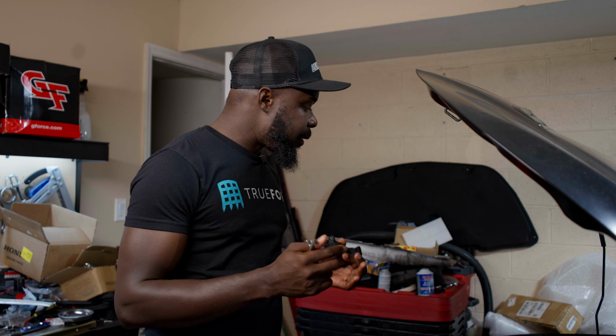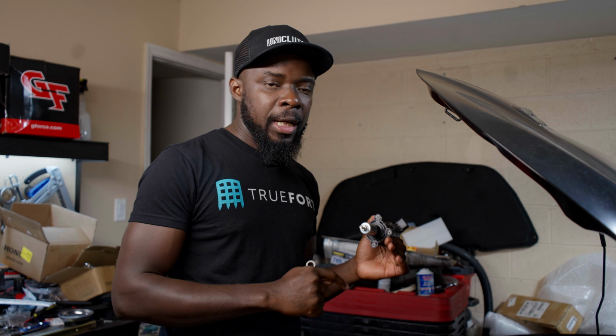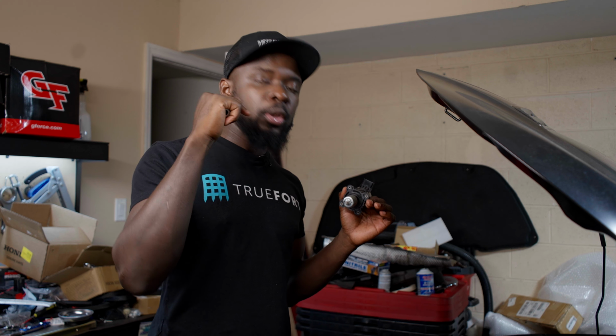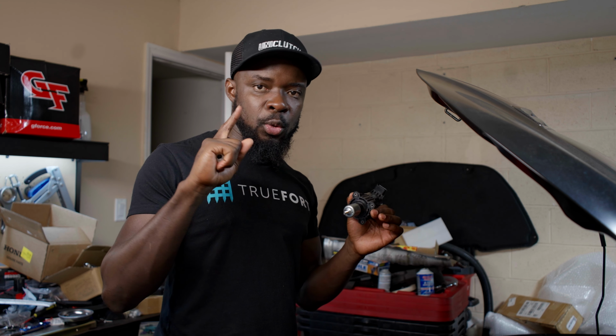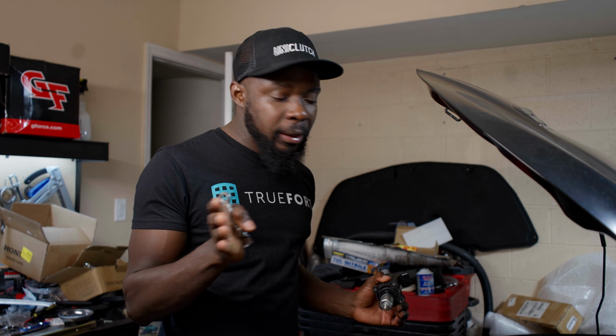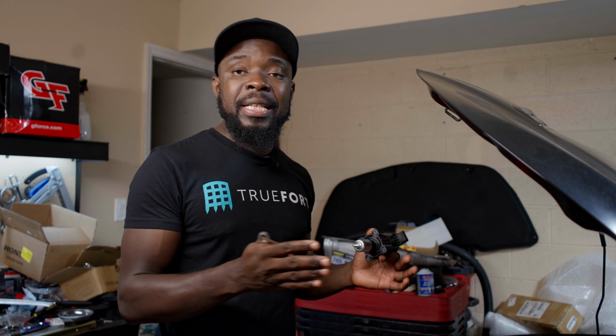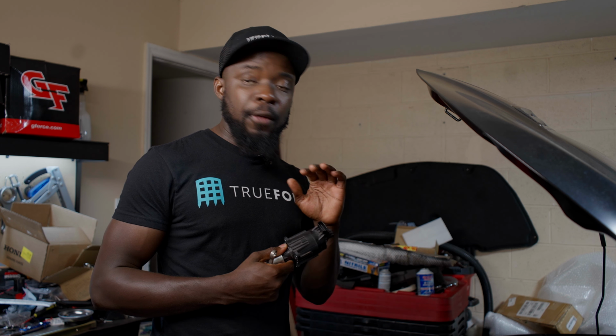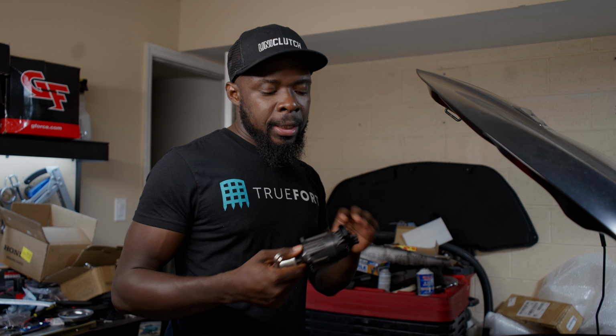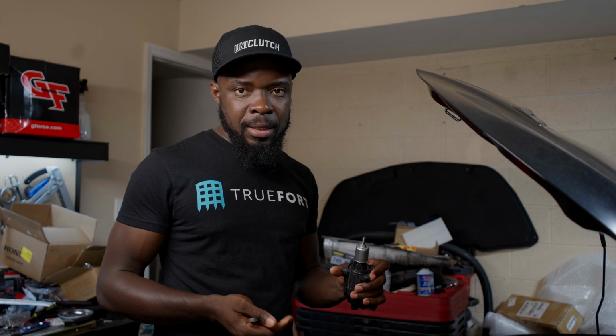Usually in proper working condition, the number is between 1 and 8 millimeters. When you press it on open, it will open and go all the way up to 8 millimeters, and when you put it on close, it will go all the way to 1 millimeter. Listen to or read the range. So if your number is out of range, then we know we have a mis-calibrated actuator.